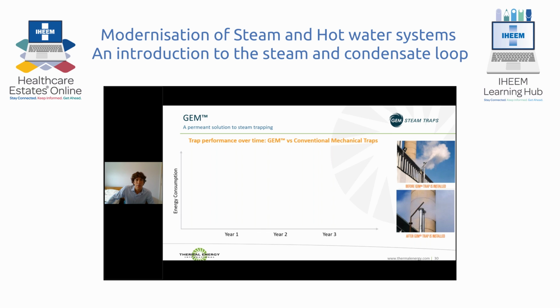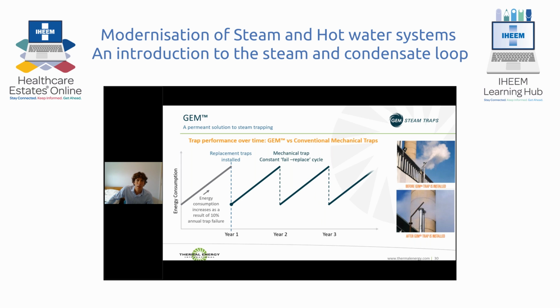So how do the GEM traps realise these savings? On this graph, we have energy consumption on the left-hand side, and on the x-axis we have time. At any point in time, the energy consumption of your plant slowly increases as the performance of the mechanical steam traps deteriorates. Until such a point, you do a steam trap survey, identify the worst actors, the failed traps, and replace them. You can then reduce the steam consumption. But of course, no sooner have you done that, steam traps start to fail elsewhere within the plant, and we are trapped in this constant fail-replace cycle. If we were to conduct more frequent steam trap surveys and replacements, then we just have more smaller peaks. This does result in energy saving, but also increases the maintenance costs.